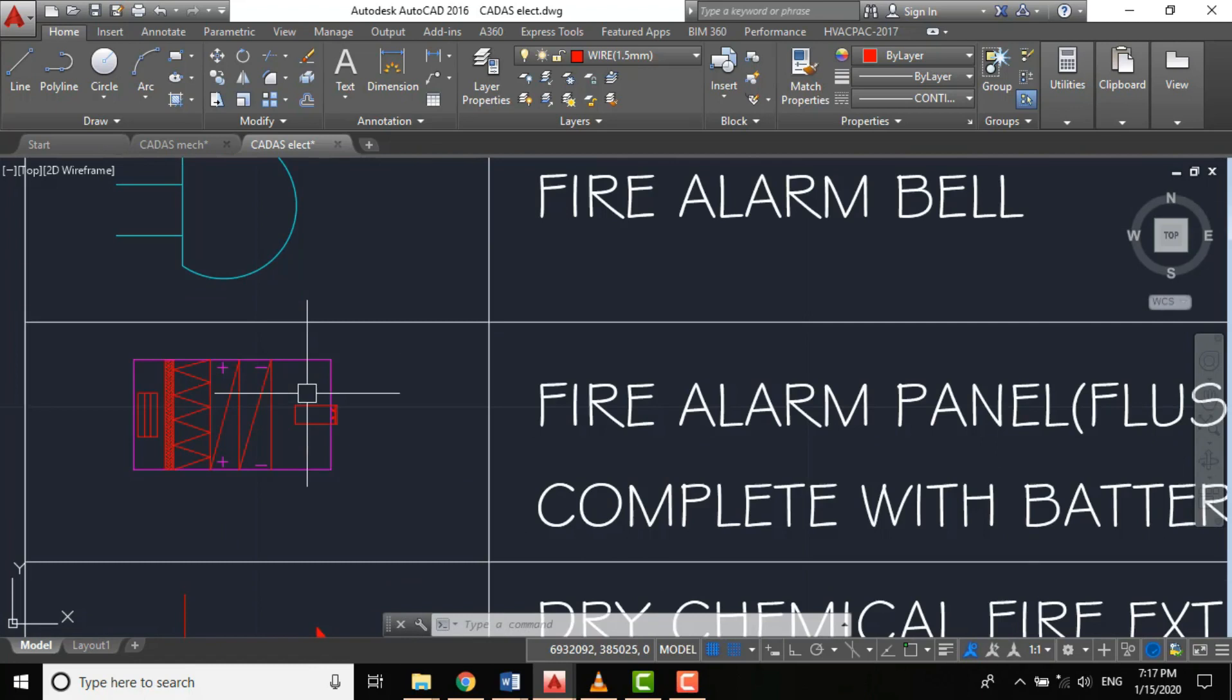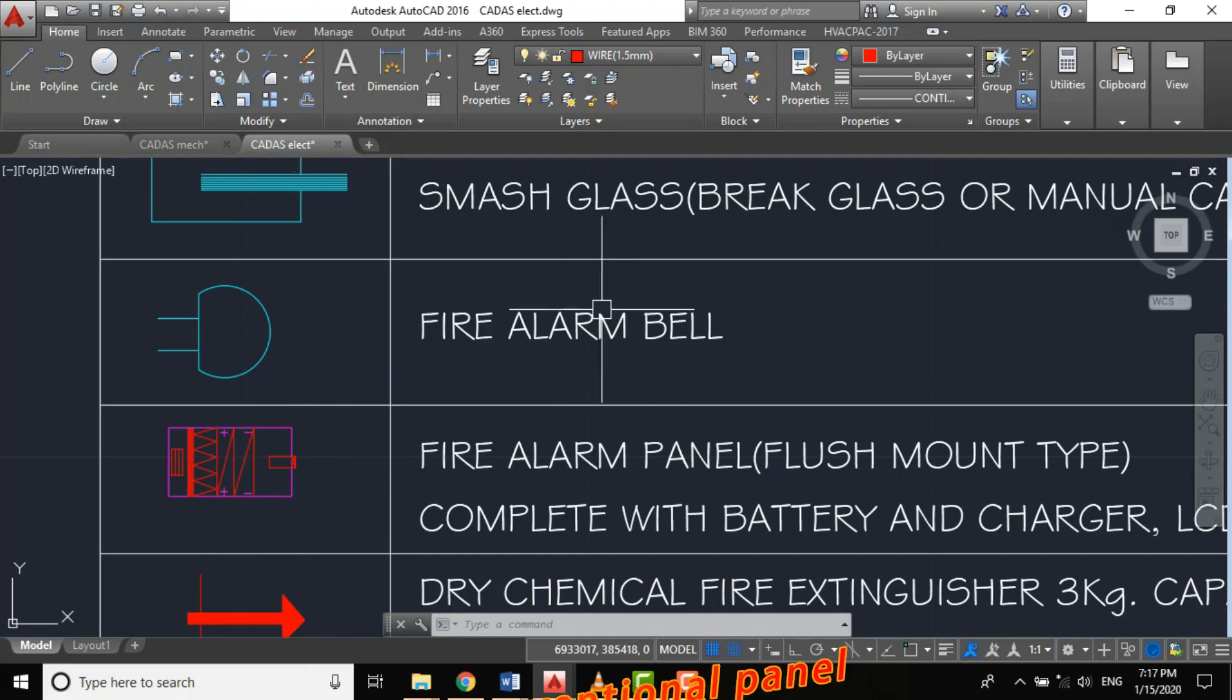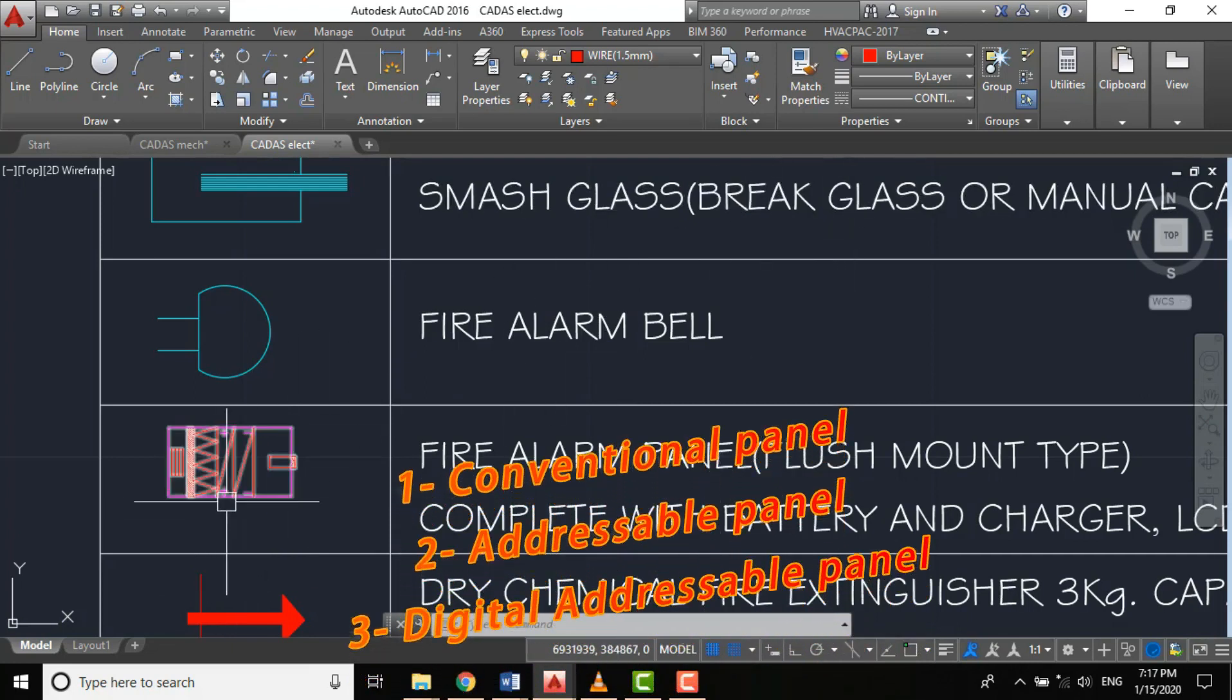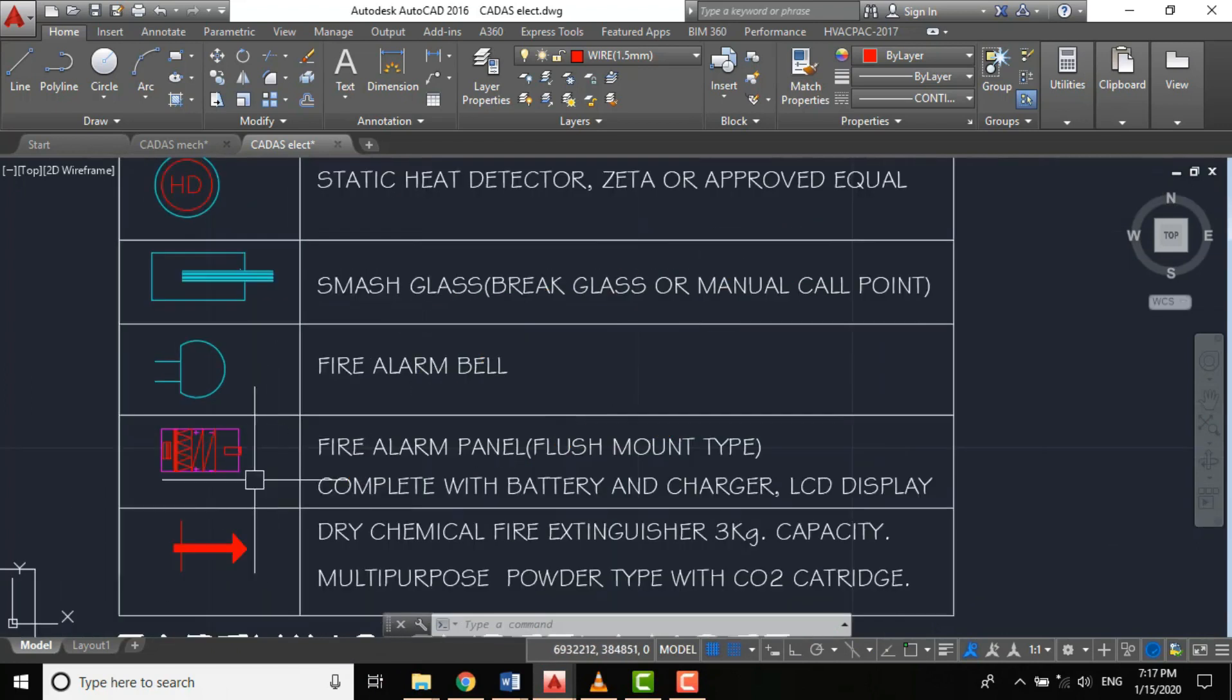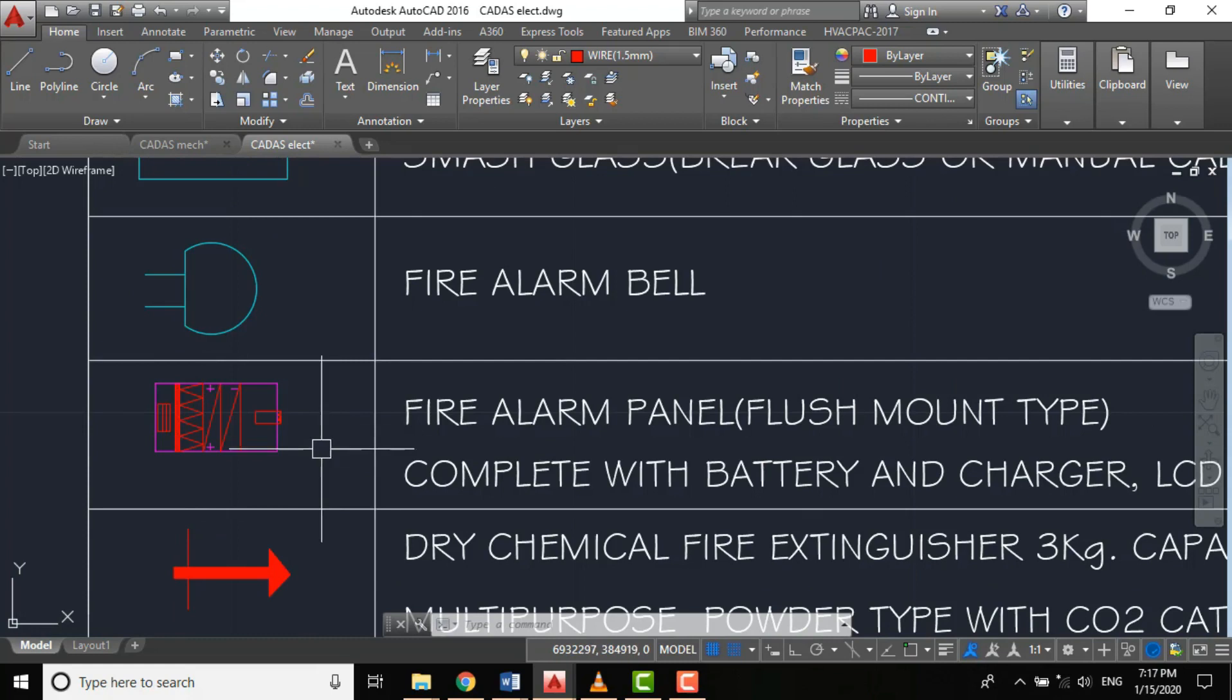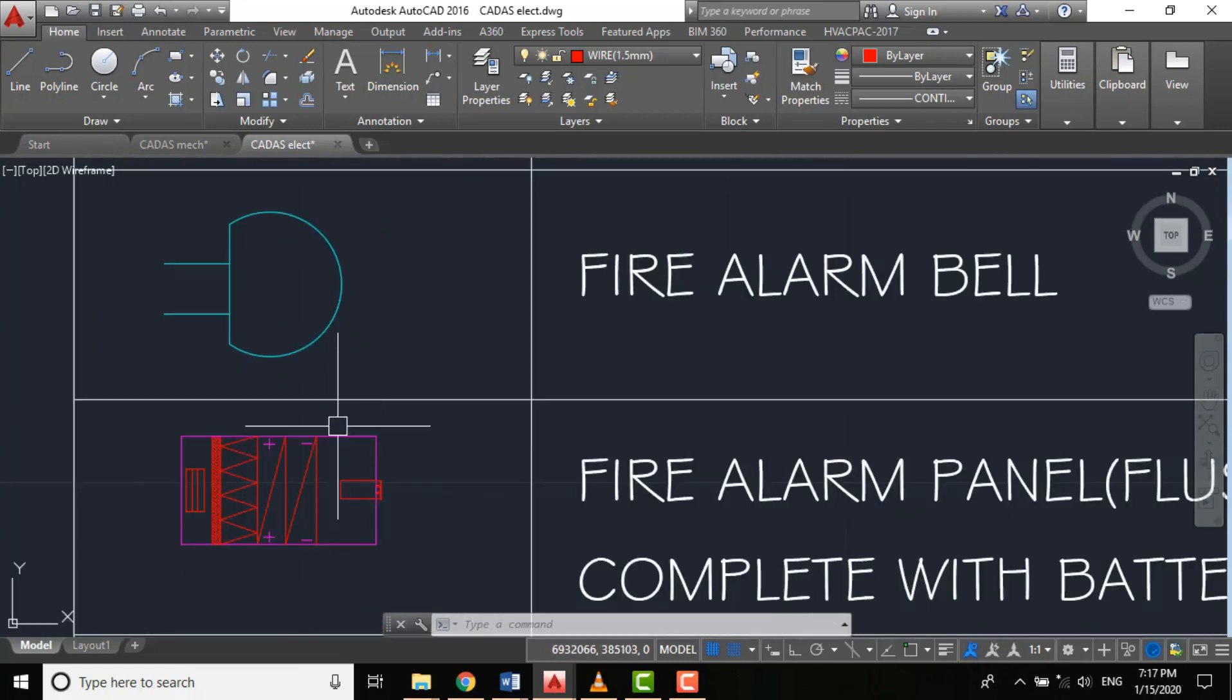We have our control panel. As I've explained, we have three types of control panel: the conventional, addressable, and digitally addressable system. For this project we'll be using the conventional system because of the fire hazard category and because it's a residential project.